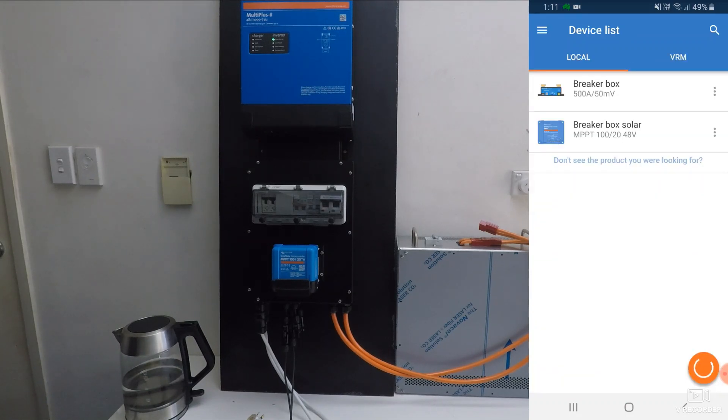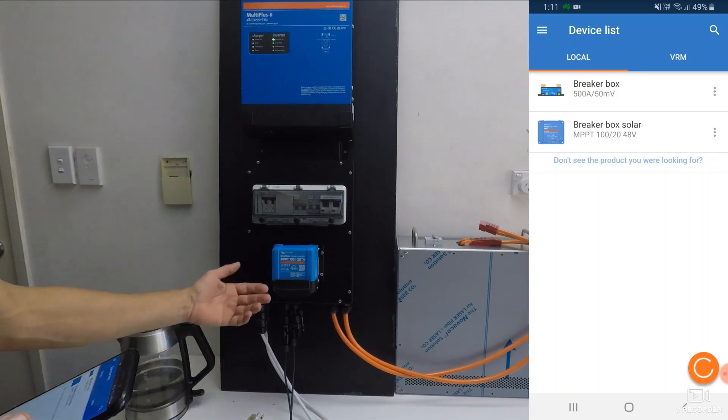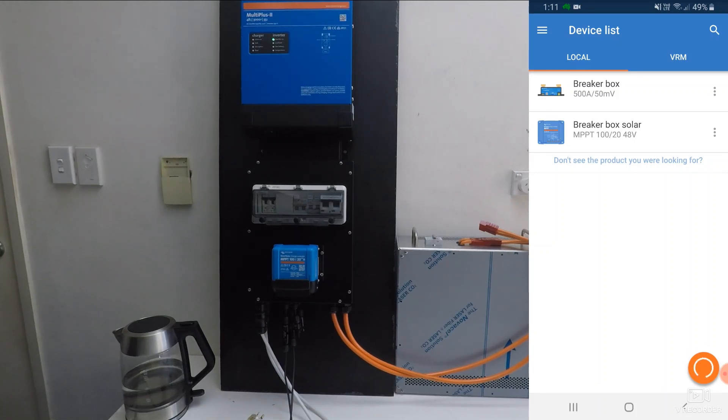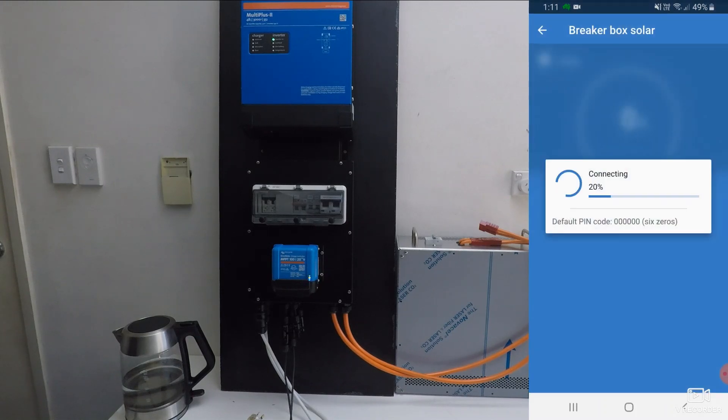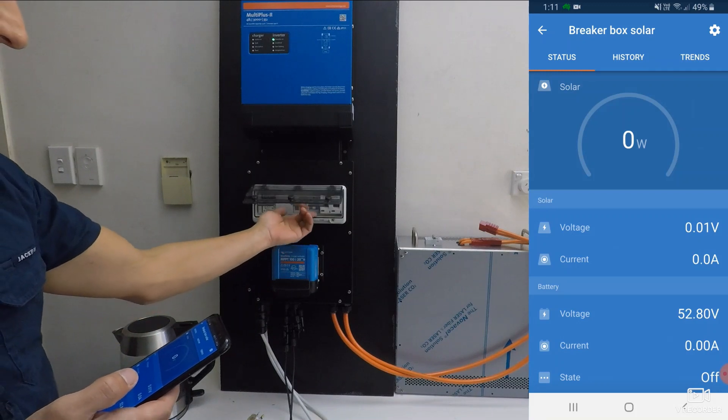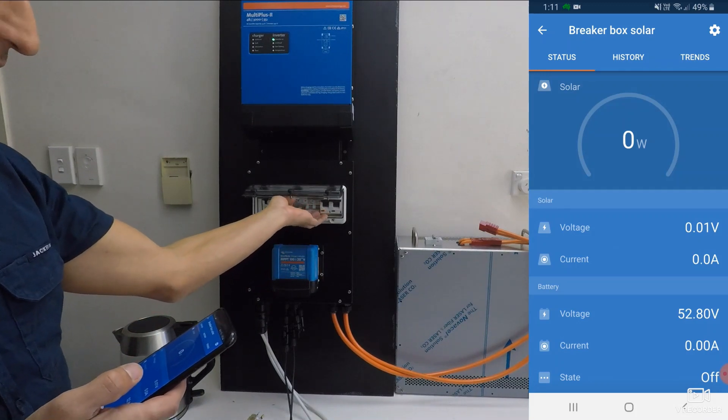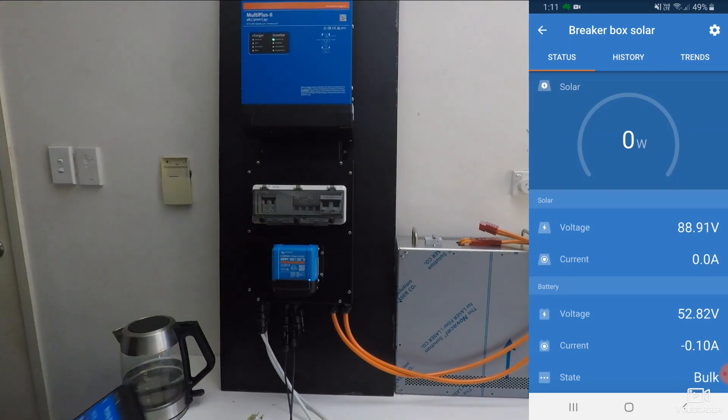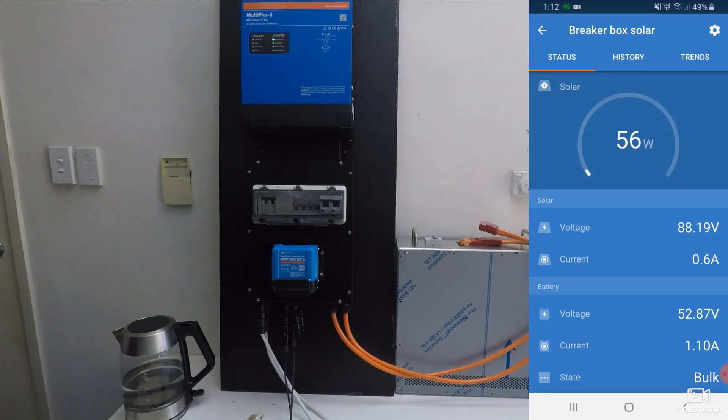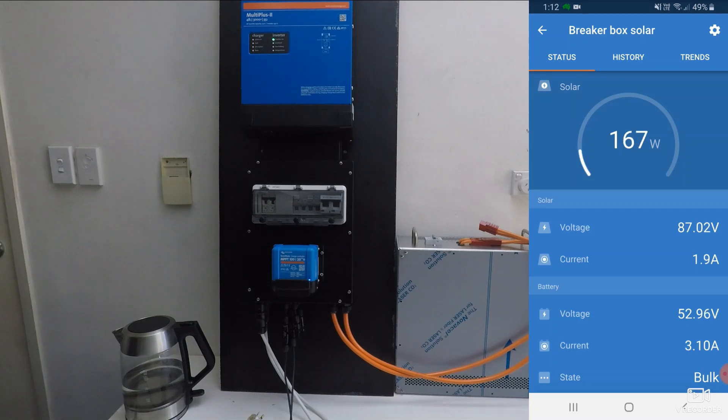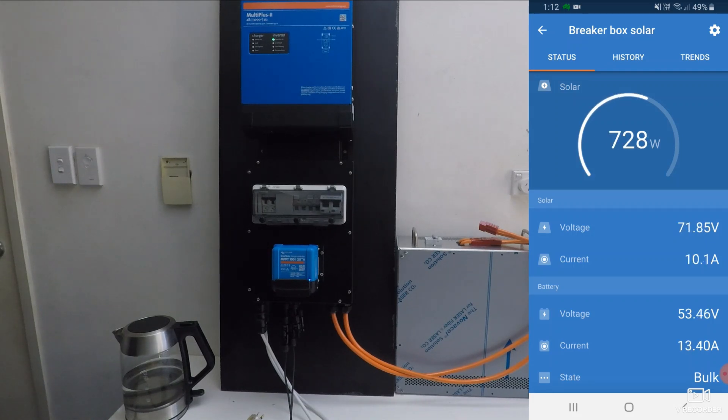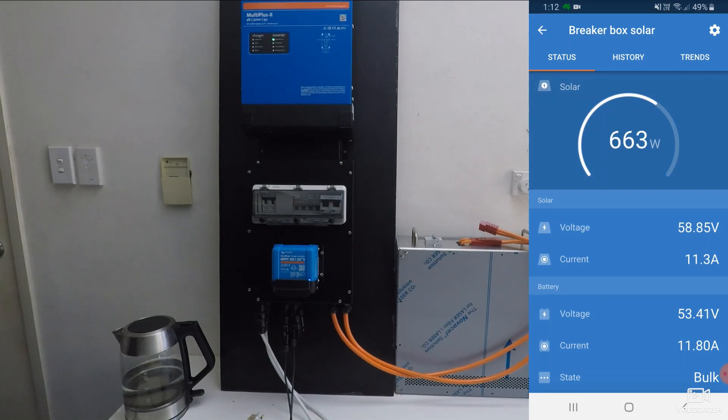Now that we've drained some power out of the battery, we can use our solar panel to charge it back up. Normally we would have the solar panel connected all the time, but in this case we're going to go to our breaker box solar, which is our maximum power point tracker. We'll connect to that, and we're going to flick our solar array on. Now I've got two 435 watt solar panels on a test rig, that's what we're using to charge. So you'll see the current and the power go up at the start, and it will find its groove, it will find the optimum place to sit at, and optimum voltage. So it will bounce around at first, but then it will stabilise.